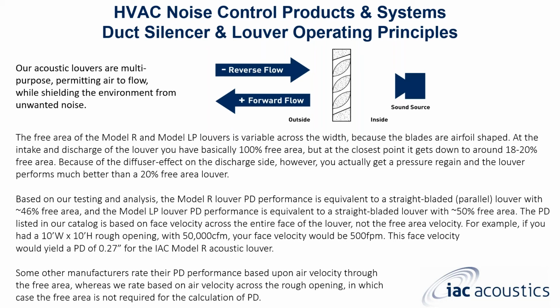Model LP is roughly 50%. So the pressure drop listed in our catalog is based on face velocity across the entire face of the louver, not just the free area. For example, if you had a 10 foot by 10 foot rough opening at 50,000 CFM, your face velocity would be 500 feet per minute. This would yield a pressure drop of 0.27 with our Model R louver.